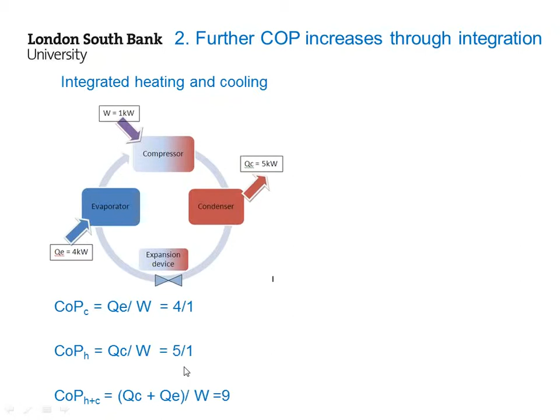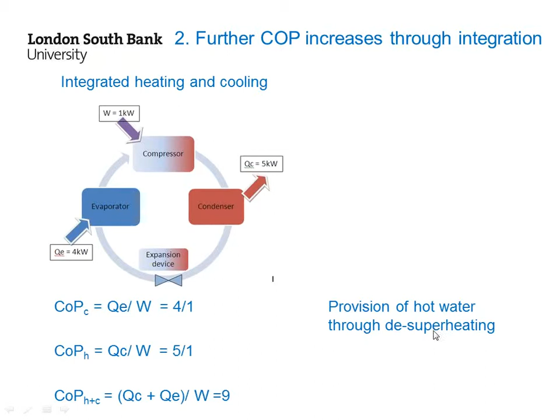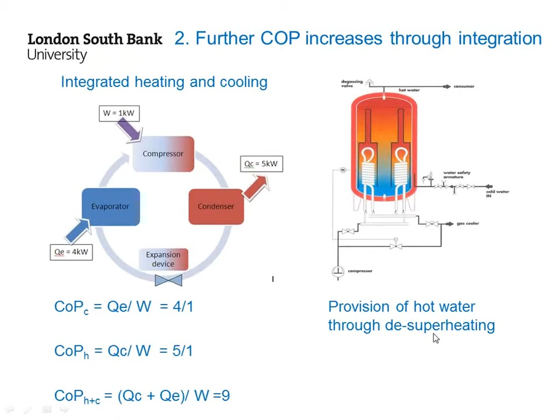Maybe by sharing heat with someone else while we use the cooling. And what we must do—this is a no-brainer—is insist that our chiller manufacturers install de-superheaters on our hot water, so we produce hot water at the same time as cooling. This is the de-superheater, it's in the paper.